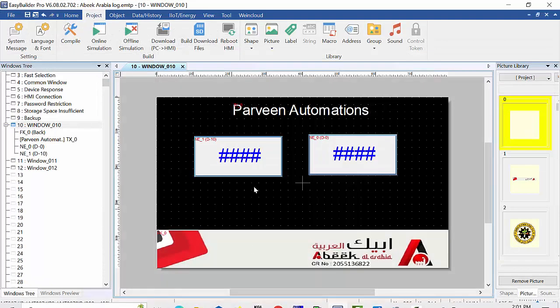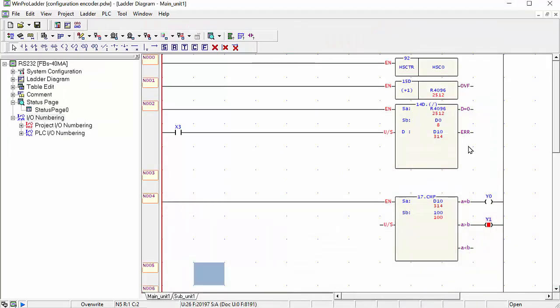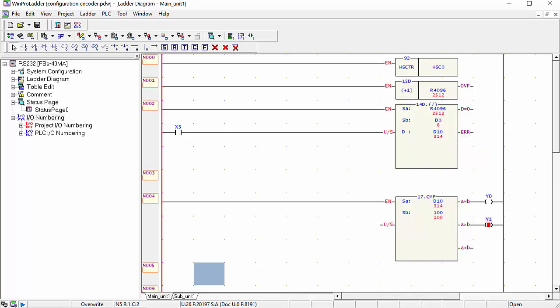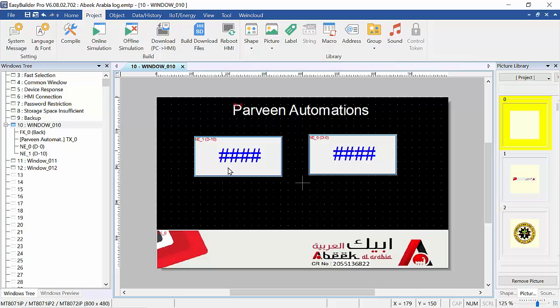Now let's go to the HMI program. I open Easy Builder Pro and here we will use D0, which represents our calibration length — for example 200 mm, 300 mm, or 400 mm. D10 will display our current position. D0 is the calibration point and D10 shows the actual position of the machine.